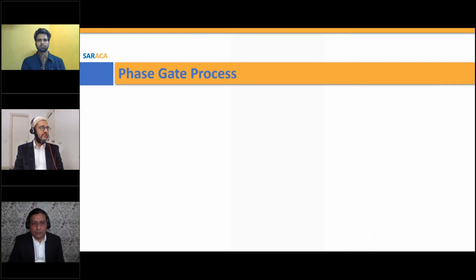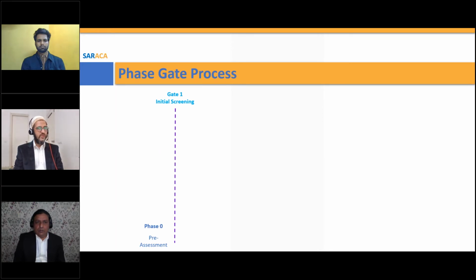Medical device development itself is a phase gate process. First you have a pre-assessment, I would say phase 0, in which, like we discussed earlier, you have all the requirements, you know the user, you know what regulatory pathway you have, and you know the technology and market value. You will see whether all this makes business sense or not. That would be gate 1, the initial screening.